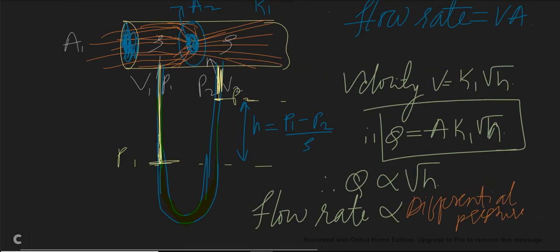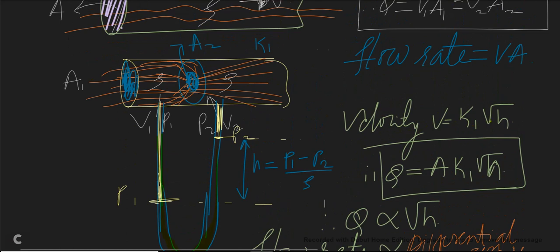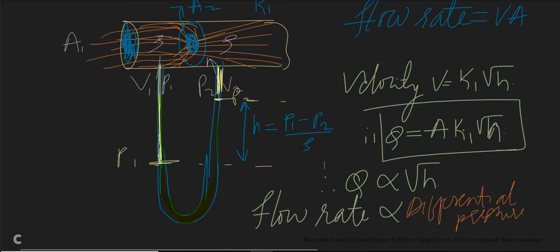This differential head can be used to measure flow rate: velocity equals K1 times the square root of H, where K1 is the restriction constant. The restriction constant K1 is derived from the ratio A1/A2, where A1 is the cross-sectional area of the pipe and A2 is the cross-sectional area of the orifice plate — A2 being smaller than A1. Substituting velocity into the flow rate formula, flow rate equals A times K1 times the square root of H. Therefore, flow rate is directly proportional to the square root of H, which means flow rate is directly proportional to the differential pressure.